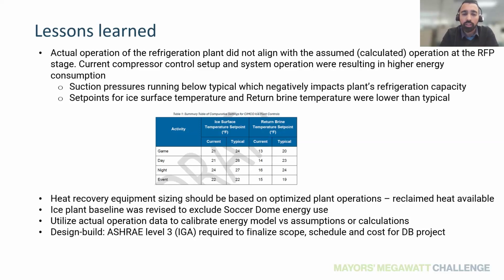One of the other lessons learned was around the suction pressure, which was running below typical levels. This essentially means there's less ammonia, less pressure going into the compressors, which creates a sub-cooling condition and makes the compressors work harder. There was no impact on quality, but the compressors were not running at an optimized state.